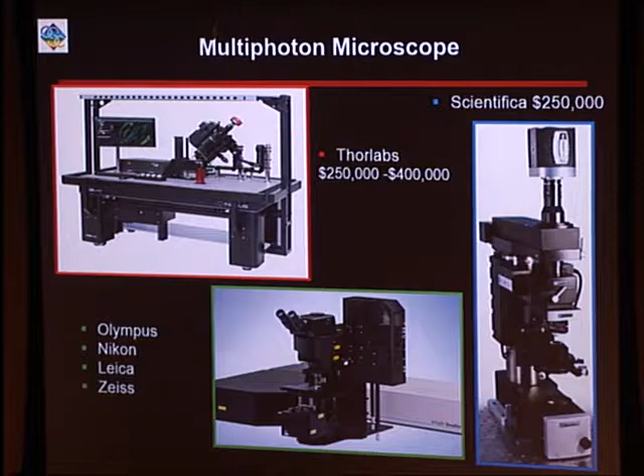So when I started, I said, oh, we can't really buy these, right? We have to build these things, and it turned out that for optics people, it's not a difficult system to build, and I don't know why it's so expensive. The optical design is very simple, right? You have basically a scan mirror right here that you scan the beam with angle, right? And then you have this telescopic system that images this mirror into the back aperture of the microscope objective, right, and that objective focuses the light down, and that's where the nonlinear signals are generated.